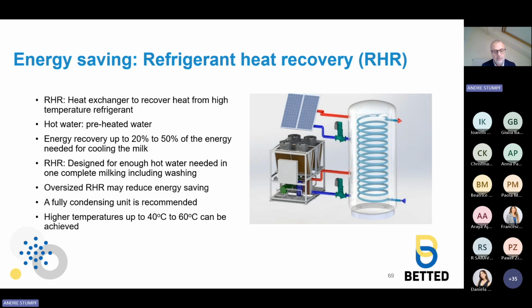In terms of components, it's important to realize that the pre-cooler and the heat recovery device both use waste heat from the milk for other purposes such as water heating. Consequently, the pre-cooler and the refrigeration heat recovery unit are somewhat in competition in terms of energy saving. And some publications recommend that a dairy with fewer than 100 dairy cows could use either a pre-cooler or refrigeration heat recovery, but not both.